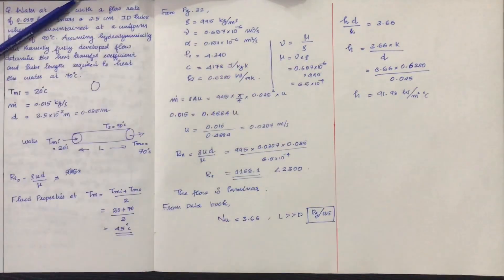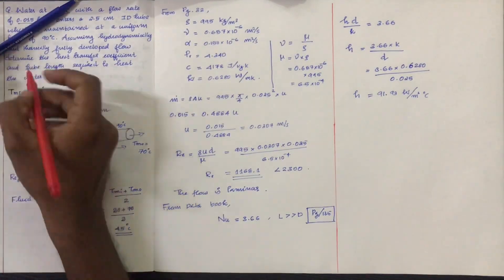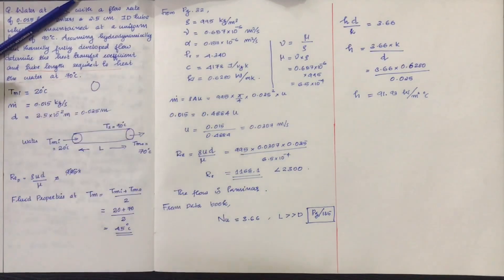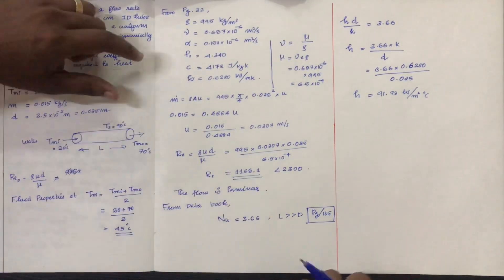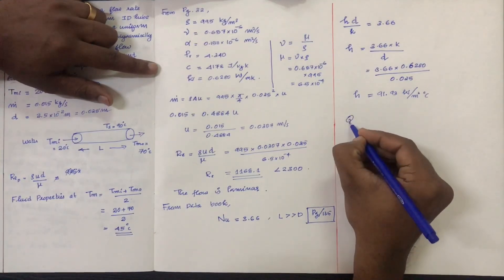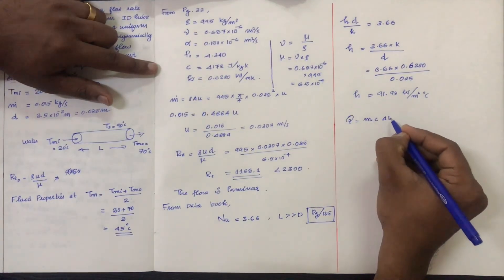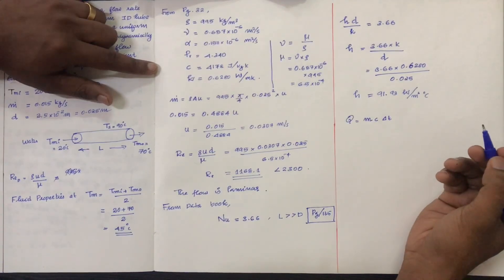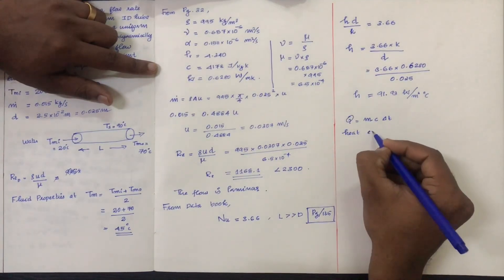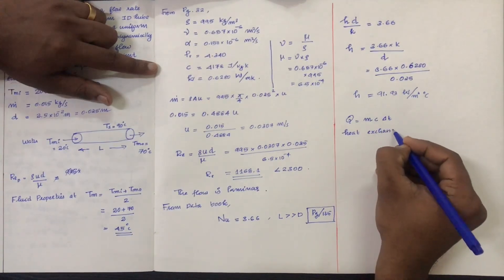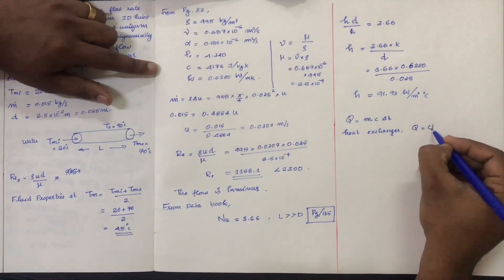Now we have to find the length of the tube required to heat the water. Using the heat exchanger equations, Q equals mass flow rate times Cp times delta T. In the heat exchanger case, Q also equals U times A times the log mean temperature difference.